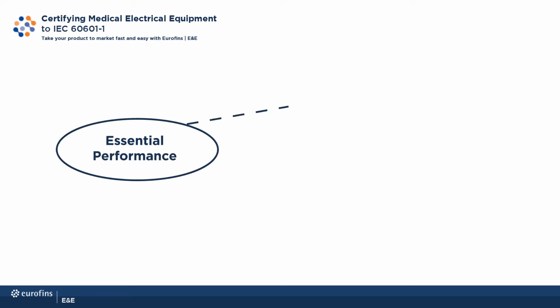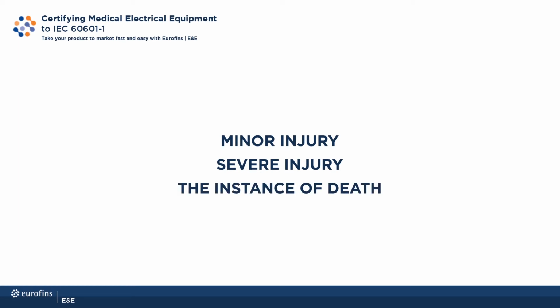Switching gears, let's discuss the next concept that is particular to medical standards, and that is essential performance. Essential performance is performance of a clinical function other than that related to basic safety, where loss or degradation beyond the limits specified by the manufacturer results in an unacceptable risk. We'll be covering unacceptable risk in depth later, but simply think of it as the possibility of minor injury all the time, severe injury fairly often, or quite possibly the instance of death.